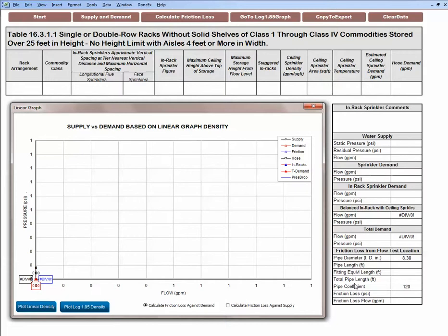I designed the software to better evaluate and manage risk. I'm an independent fire protection consultant for several insurance carriers, and I visit many facilities, some of which include Mega Warehouses. This particular demonstration evaluates adequacy of protection in a Mega Warehouse containing Class 4 commodities stored to 50 feet high on double row racks.